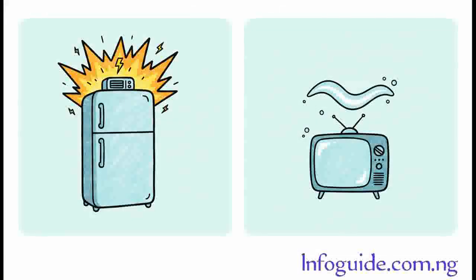So, two of the biggest trip-ups are surge current versus continuous load. This is a fascinating dynamic. Continuous load is simply the steady, baseline power required to keep an appliance running once it's already turned on and humming along nicely. But surge current, man, that is the massive, instantaneous power spike required just to start certain appliances up in the first place, particularly anything with a motor. Think refrigerators, air conditioners, water pumps. That starting spike can easily be double or even triple the running wattage. You might do the math and think you have enough continuous power, but if your inverter's kVA rating can't handle that massive momentary surge, the whole system will just trip and shut down the very second your fridge kicks on.